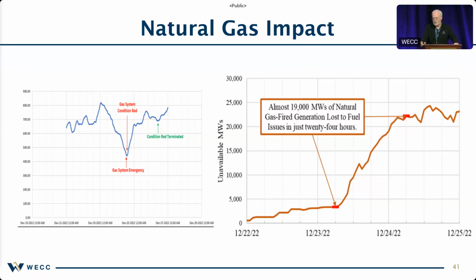As the pressure drops on that pipeline, they enter an emergency condition. You can see on the right, 19,000 megawatts of natural gas fired generation lost to fuel issues in just a 24-hour period. So definitely there was freezing at the wellheads and stuff during this event, but the natural gas usage and the natural gas impact also significantly affected generation in this event.